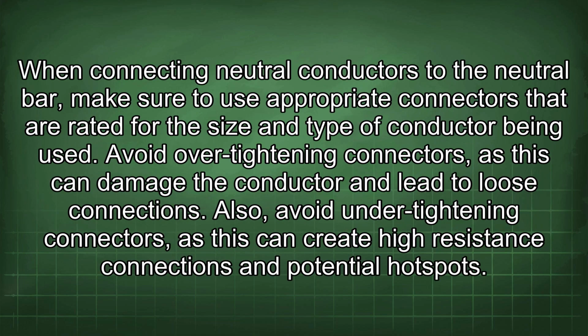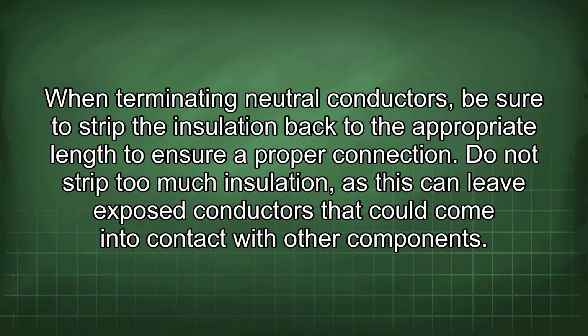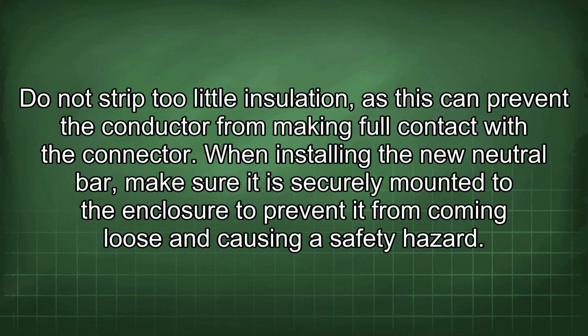When connecting neutral conductors to the neutral bar, make sure to use appropriate connectors that are rated for the size and type of conductor being used. Avoid over-tightening connectors, as this can damage the conductor and lead to loose connections. Also, avoid under-tightening connectors, as this can create high resistance connections and potential hotspots. When terminating neutral conductors, be sure to strip the insulation back to the appropriate length to ensure a proper connection. Do not strip too much insulation, as this can leave exposed conductors that could come into contact with other components. Do not strip too little insulation, as this can prevent the conductor from making full contact with the connector.